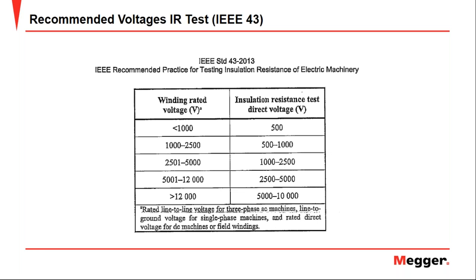For example, a 480 volt motor. According to the table, the test has to be done at 500 volts. If we take the case of a 4000 volt motor, the range will be between 1000 and 2500 volts. We must know this standard is valid only if the OEM doesn't indicate the voltage level we must reach in the test. But if in the manual or a user guide, the OEM clearly establishes the voltage level of the test, this should be taken as true, and the IEEE 43 standard should not be considered.